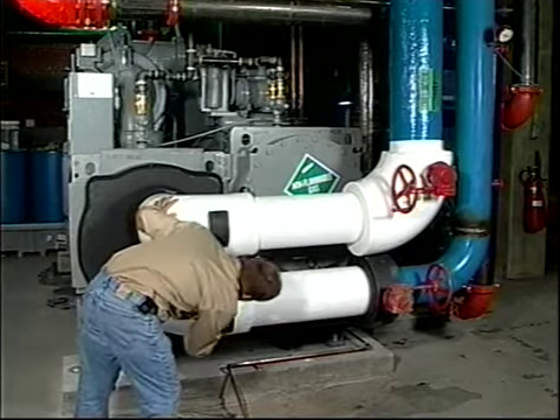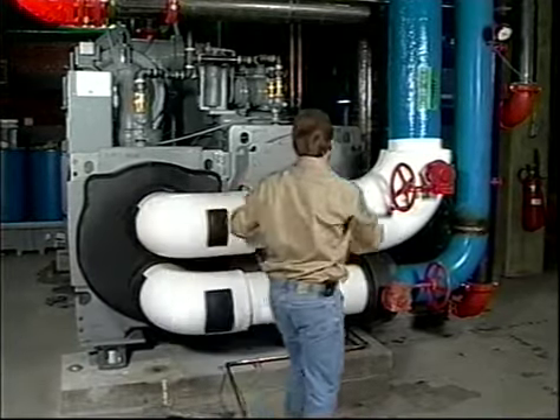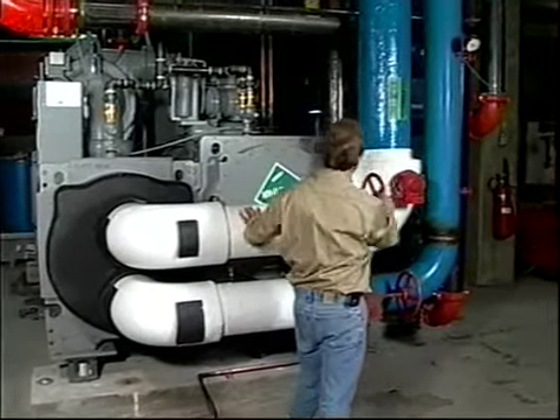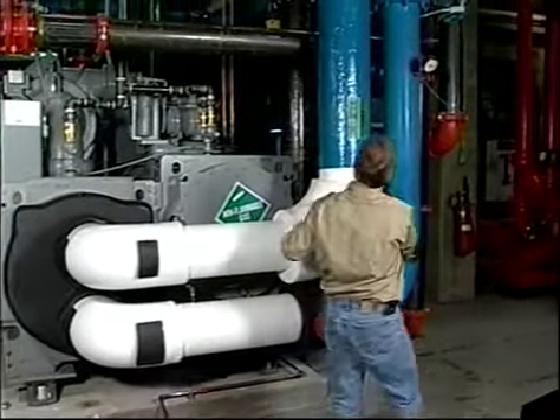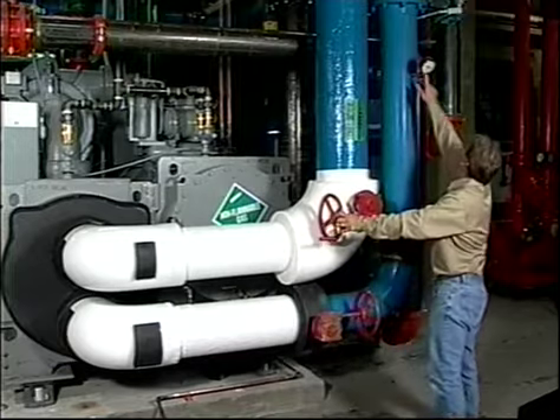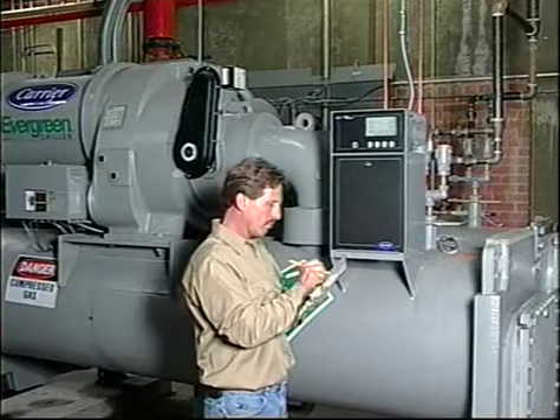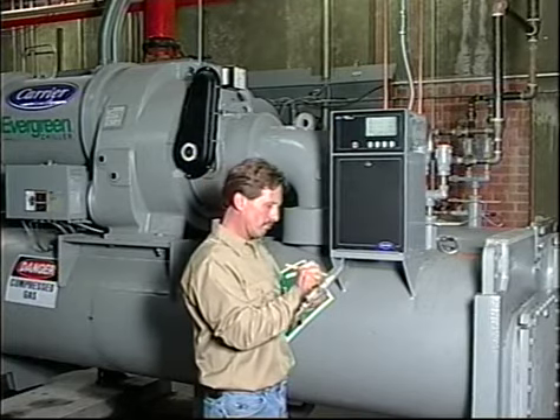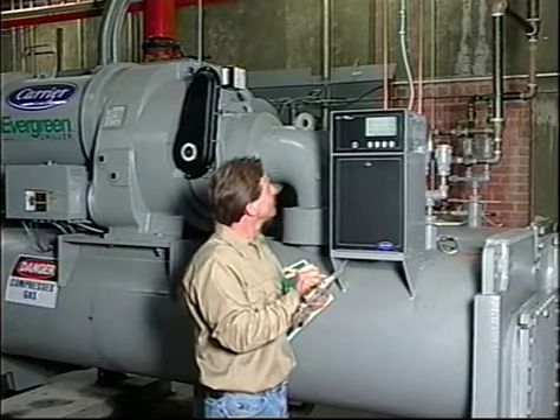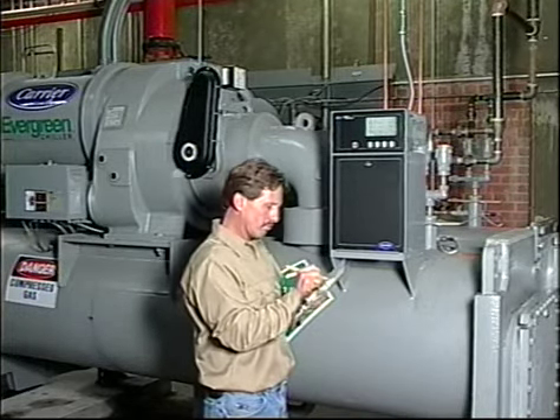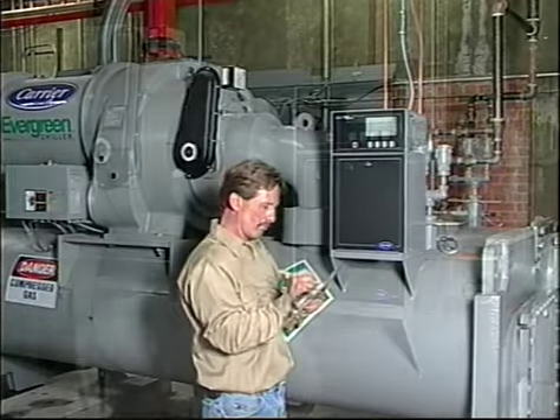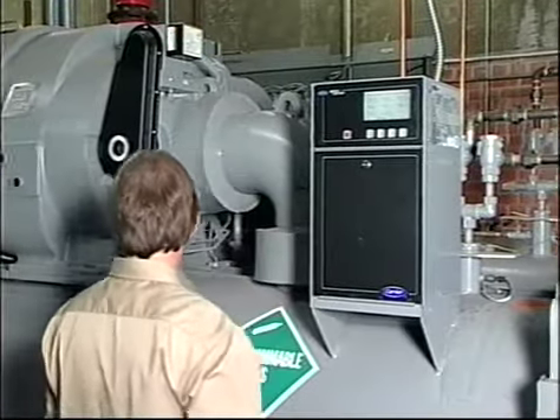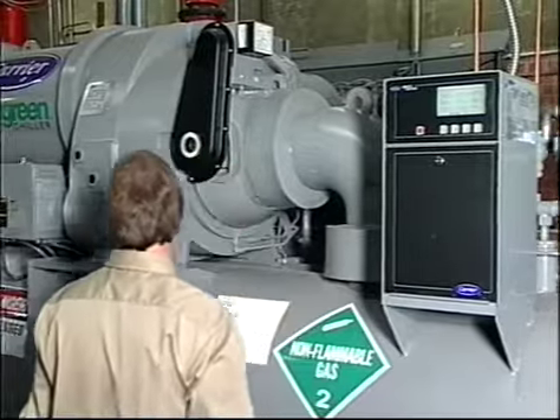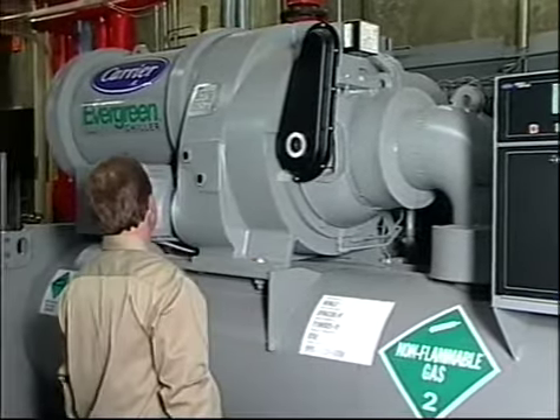After all, it's your equipment. The better you understand it and the better care you give it, the better it will serve you. So let's look at some of the things that need to happen. On a daily basis, we've already covered the operating conditions that should be read, entered in your log, and reviewed. In addition to that, you need to be listening for any unusual sounds or vibration, and you must be alert for the possibility of refrigerant leaks.